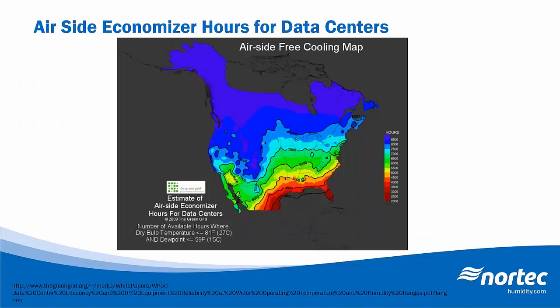So let's talk a little bit more about airside economization. Airside economizers use fans and louvers to draw in cooler outside air, which is mixed with warmer return air, in order to maintain a specified environmental condition within the data center.